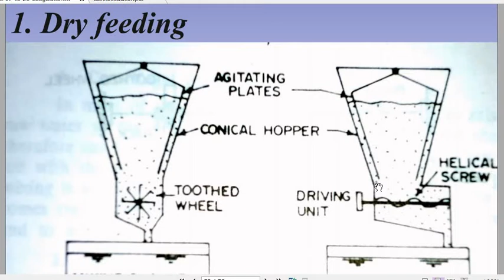In the toothed wheel, dry coagulant is filled into the compartment, and the agitating plates are placed over it, and this conical hopper will concentrate the coagulant at the bottom. At the left hand side you can see the toothed wheel, and at the right hand side you can see the driving unit, that is the helical screw is provided at the driving unit, and at the left hand side is the toothed wheel.